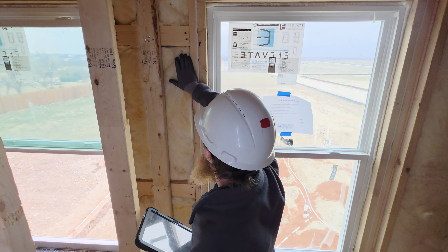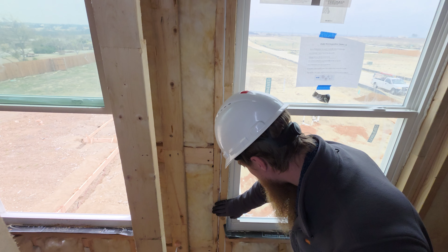If they're expecting you to use a lot more insulation than you're actually installing, you're going to have a problem, and the other way around too. If you're using a lot more insulation than they put in the manual J, you're going to have a problem. All of these things mean the HVAC has to be designed correctly for the home being built.